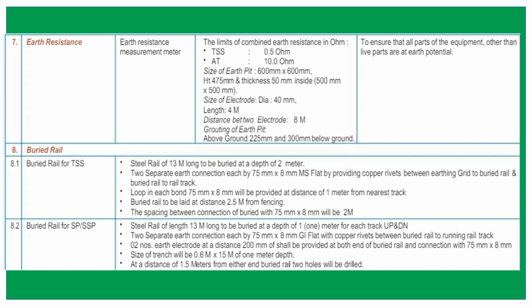Earth resistance measurement meter, earth tester is there. Earthing resistance you can measure with it. And for TSS, the combined earth resistance should be 0.5 ohm. What is combined earth resistance? We are forming a mesh 600 millimeter below the surface level of the TSS, and this mesh is made of steel rods and earth electrode or earth cone, a combination of earth cone and steel rods. Its area is almost the switching yard. Below the switching yard, it will spread throughout the switching yard, and all structure will be connected with this earthing mesh.